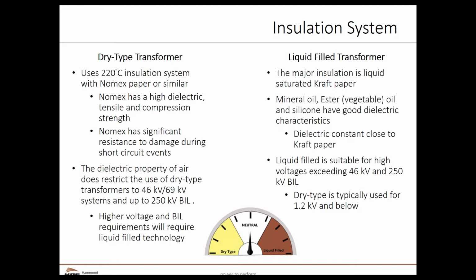The issue is, and everybody's seen lightning, at a certain point, the dielectric strength of air tends to lose some effectiveness. Generally for VPI transformers, that would be up to about 46 kV class. Again, we've seen some cast transformers claim to go up to 69 kV class, but for the most part, we're looking at 46 kV and below, and up to 250,000 volts or 250 kV BIL ratings. Anything above that, and you're probably going to be looking at liquid.